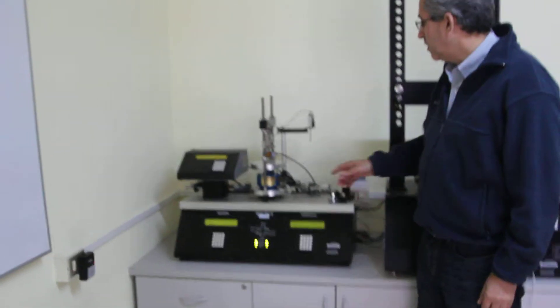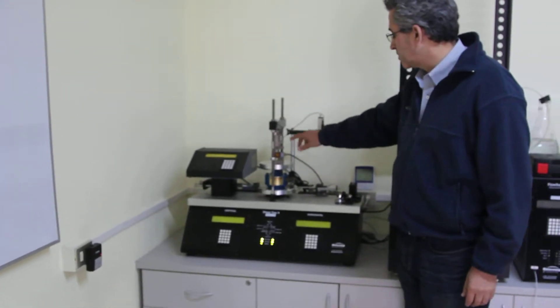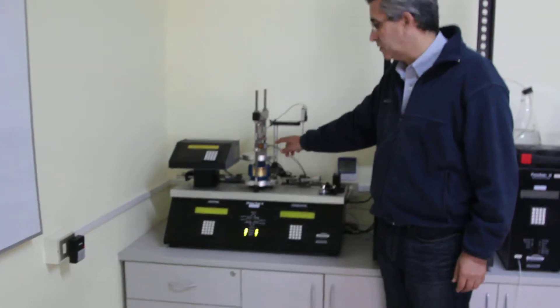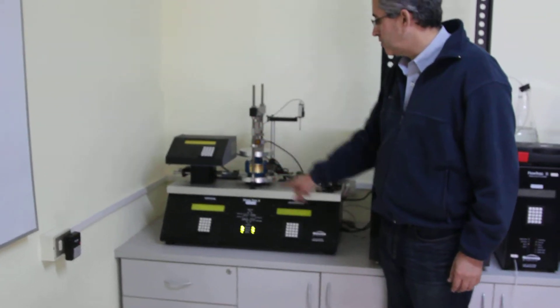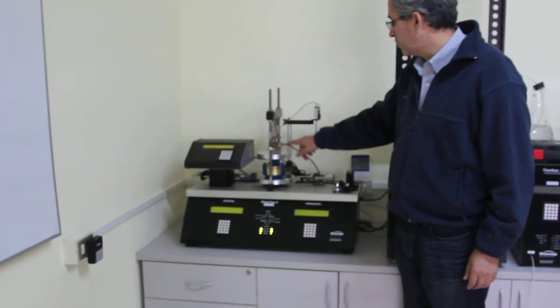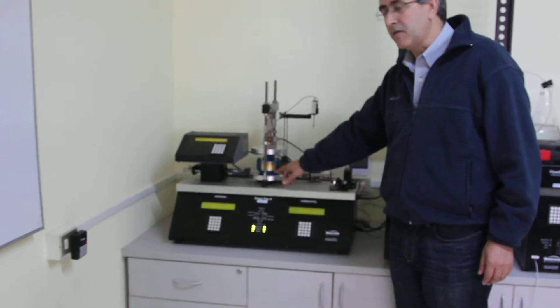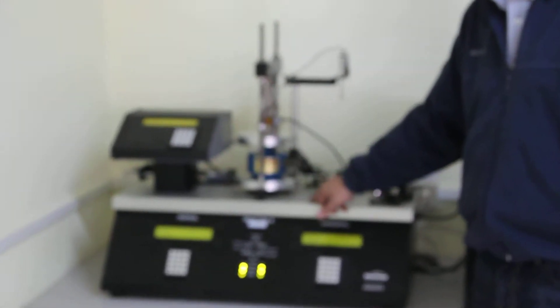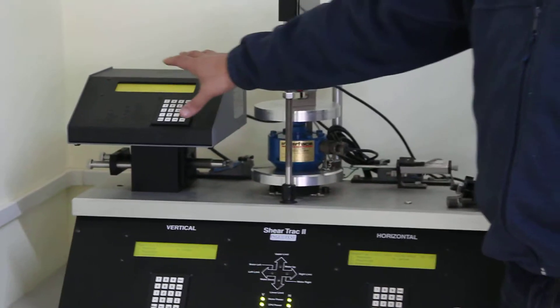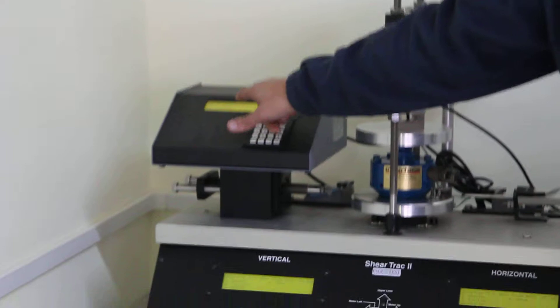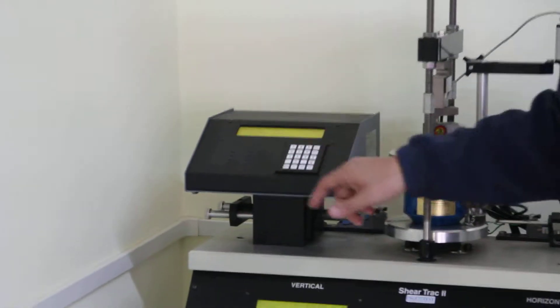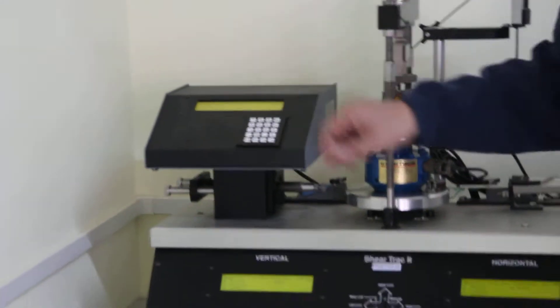We are doing the calibration of the load cells. There are two load cells, the vertical and the horizontal of the direct shear machine. In order to do the calibration we need a reference calibration which is an interface gold standard calibration type or grade load cell that has a digital readout box where we can see the load reading there.